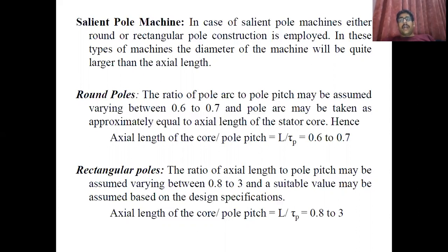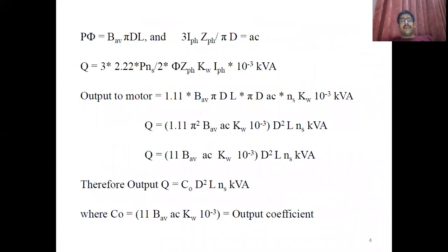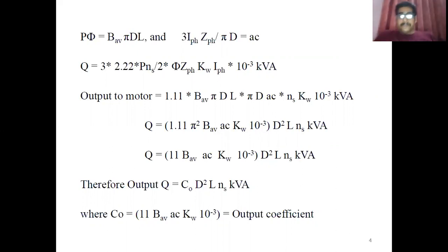As discussed in our previous video, in case of a synchronous machine the output equation is: Q = C₀·D²·L·ns, where C₀ = 11·Bav·ac·kw × 10⁻³. Here Bav and ac are the specific magnetic loading and specific electrical loading, and kw is the winding factor with a value of 0.955. By changing the values of specific magnetic loading and specific electrical loading, you can change the output of the synchronous machine.